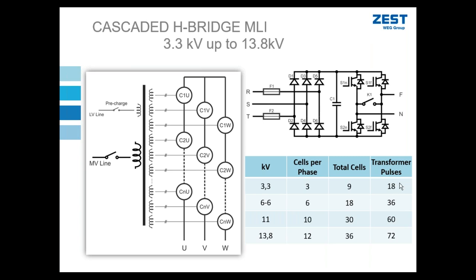So that is the reason you can see we naturally increase the number of pulses as we increase the number of cells. Why? Because we've got to put in additional secondaries anyway. So we may as well make use of that fact, even though earlier on we said, look, 12 pulse, 18 pulse, going beyond that is not really giving you much return for your added complexity. Here we've got to increase our complexity due to the nature of the switching, not the harmonics, but I may as well make use of that complexity that I'm adding, that number of secondaries, to also increase the number of pulses to improve my input harmonics.